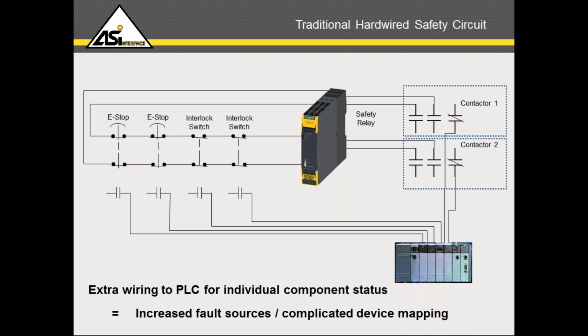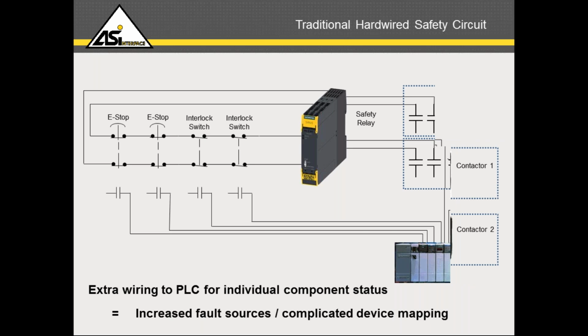Each wire has to be labeled, which is an additional labor cost, and they all have to be landed, sometimes multiple times, like in marshalling panels or junction boxes, adding even more labor cost. Not to mention the opportunity for wiring errors. We're all human, we've made the errors, and that potential is really enormous the larger the application, and that could potentially cause added complexity all the way from commissioning through startup and into the maintenance phase down the road. So you can see that the costs are really adding up for a traditional safety solution using hardwire.